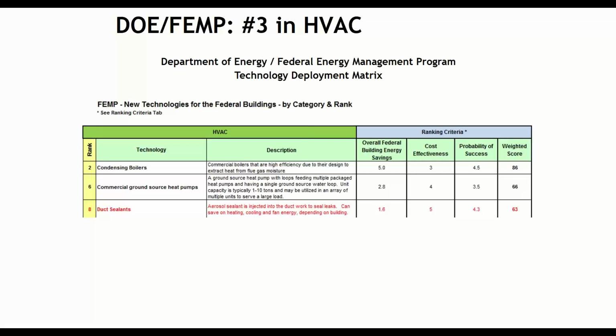This is just showing you, I should have probably blown this up a little bit bigger, one of the federal studies on some of the technologies that can be utilized to save the most energy on existing buildings. And we specifically highlighted number 2, number 6, and number 8, because those were the top HVAC things. The other stuff on the list wasn't HVAC. And I only care about HVAC, so I only have that on here. As Glenn was just talking about on the intro slides, condensing boilers, upgrading to a boiler, and getting your boiler working efficiently is on that list. It's one of the biggest things you can do for a large commercial building.